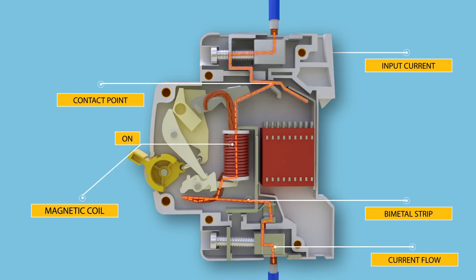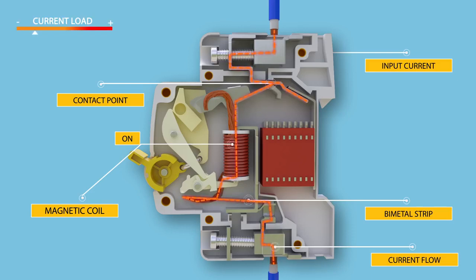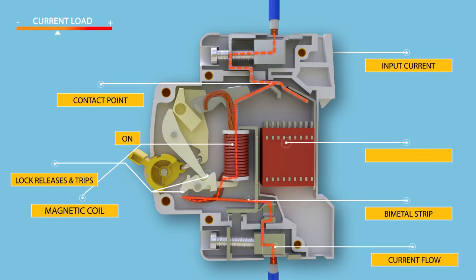Under overload condition, the current through the bimetallic strip causes a rise in its temperature. The heat generated within the bimetallic strip is enough to cause deflection due to thermal expansion of metals. This deflection further releases the trip latch and the contacts get separated. The visual indication of this trip can be observed by automatic movement of the operator to the off position.